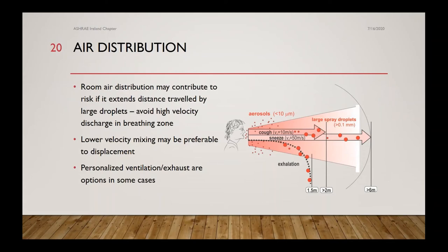The concern about air distribution is that if we have strong air currents and also poor ventilation, those air currents may carry larger droplets away from an infected person and essentially extend the radius for close contact infection. A lot of the guidance produced for industrial facilities has recommended not using pedestal fans, which are very common for providing convective cooling in environments that aren't normally mechanically cooled, and also not using personal fans in workplaces. Personalized ventilation and personalized exhaust can be effective air distribution modes, but the larger air currents from air conditioning equipment like mini-split systems that often produce fairly strong air flows are a concern.